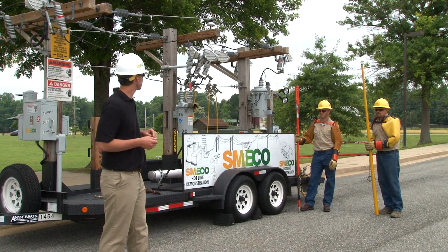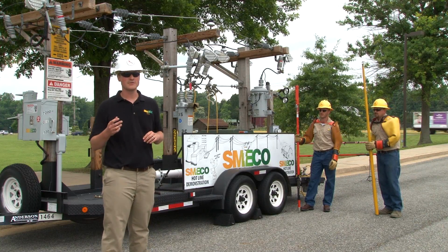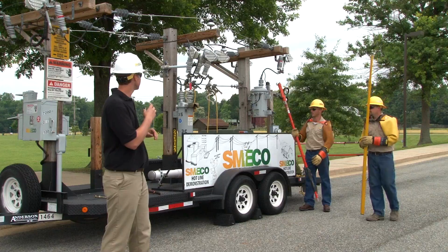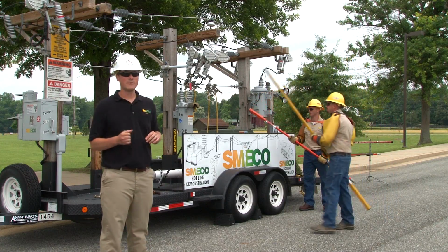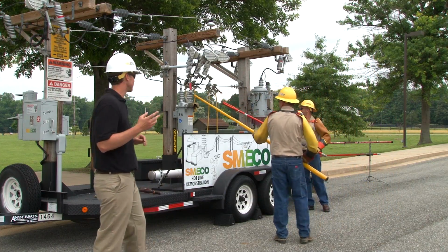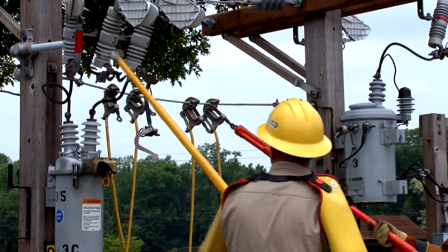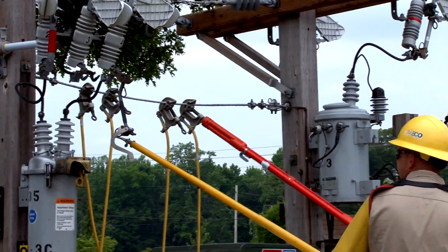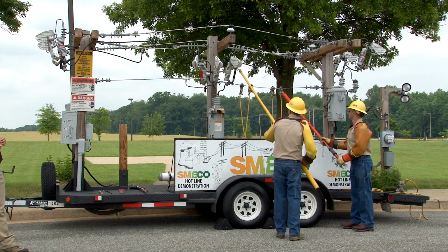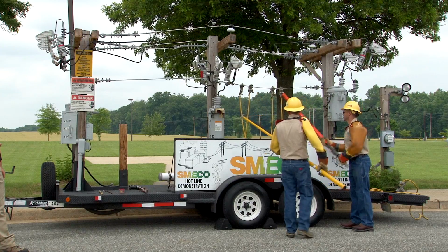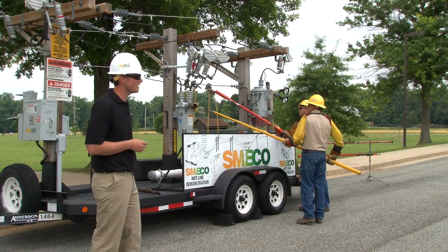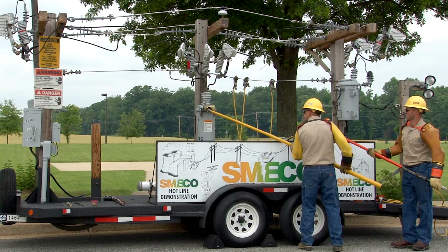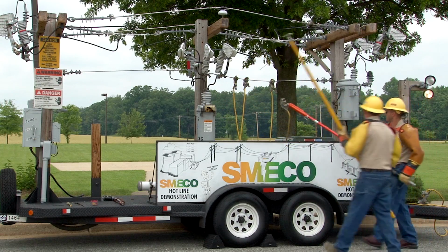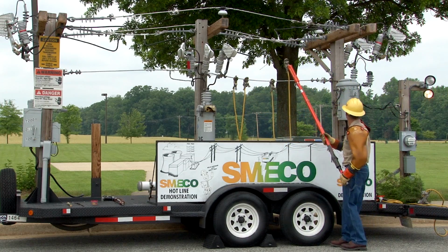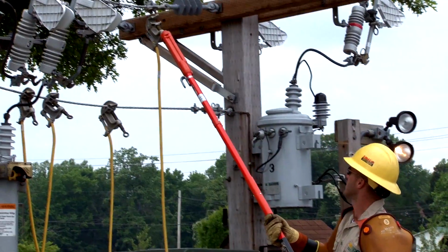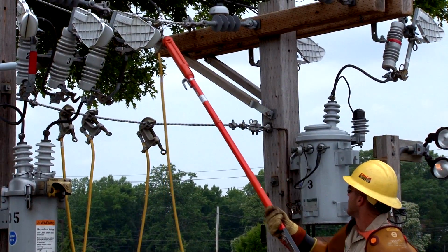So what Jeremy is going to do right now is take a protective ground, turn the recloser into reclosing mode, and bump the ground into the overhead conductor and show you that we don't necessarily have to send a truck out when a recloser is in operation. Notice the lights are off now. The recloser is on. He's going to take that protective ground and bump it into the phase, the same as you saw with the explosion. Notice the light goes on, goes off.